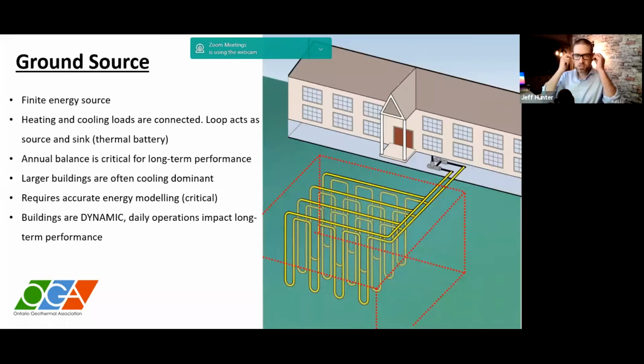Then we look conversely at the geothermal system, which is a finite energy source. I want to be careful how I describe this - I mean finite in the sense that you see the red dots there, the loop field underlined in this particular building, which is a three-dimensional block of earth that has become our energy source. If all things are done properly - design and operation - that is essentially an infinite source of energy; the building will operate infinitely off that thermal energy source. But it's finite in that it's truly defined in that sense.